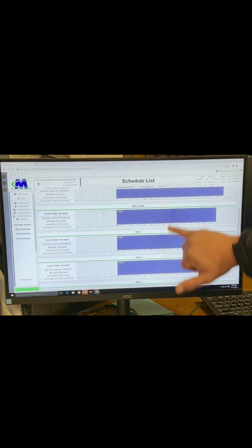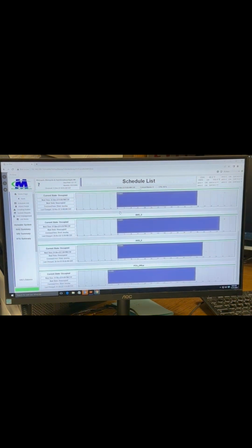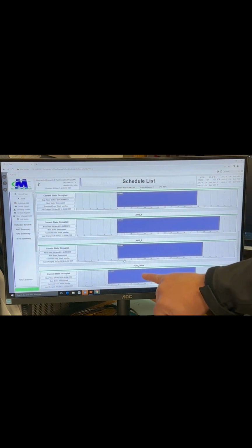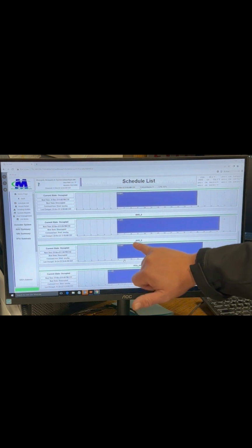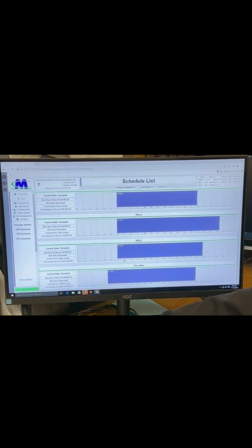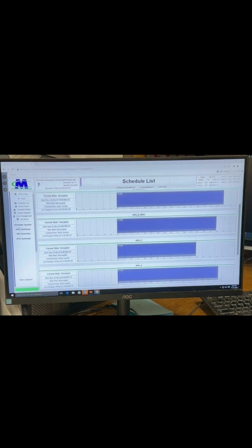So you're going to see 4 more schedules in here to edit or do with as you please. And I'll probably have Kyle do it. It's not going to be named this. I'm going to name it chapel. Got it. And then RTU1 and 2 will be tied to said chapel schedule. There's one thing with this product I don't like. I wish they would have a list of what pieces of equipment were tied to each schedule. The Tridium product doesn't do that.